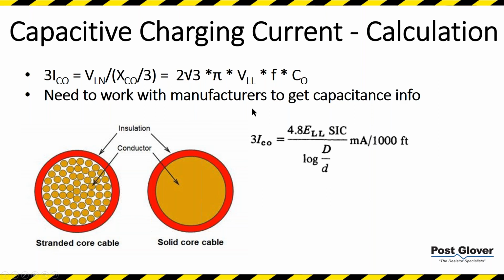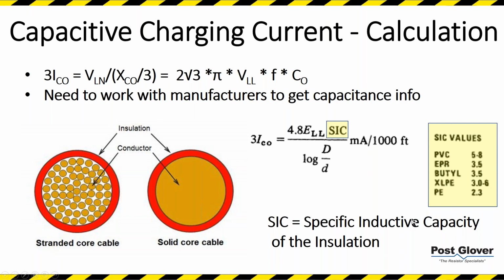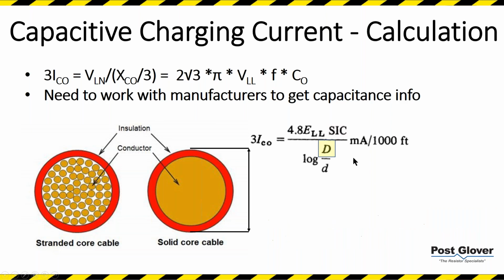As long as you know the size of your wire, essentially you have a derivation of the formula, and so you have your same charging current. This is your line-to-line voltage. SIC is the specific inductive capacity of the insulation. Do you have to know exactly what that means? No, I'm not sure I can explain it to you. All you really need to know is that, depending on what you're using, you can use a certain factor there. Then you have the diameter of your overall cable and the diameter of your conductor. So you can calculate this fairly simply, and usually the wire is about 80% of the capacitive charging current calculation. So you're going to have the vast majority of that system done.